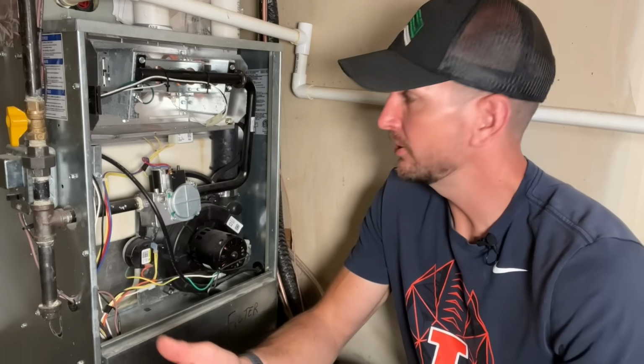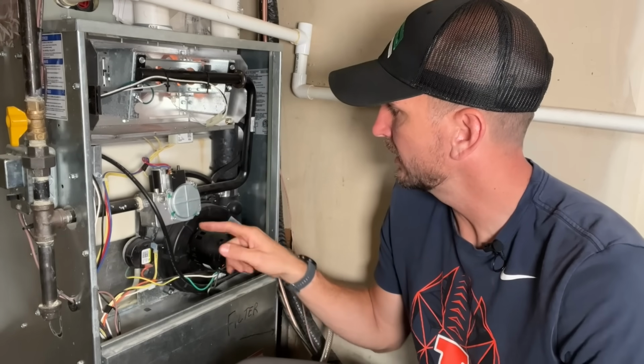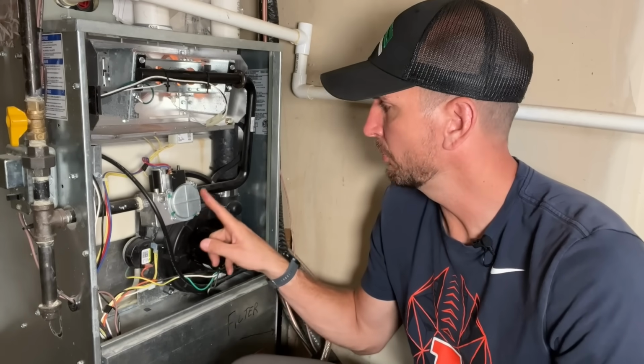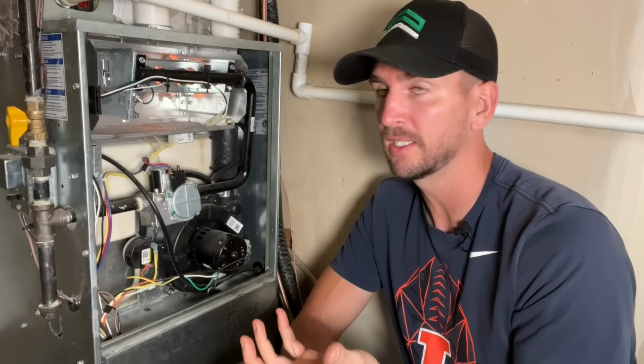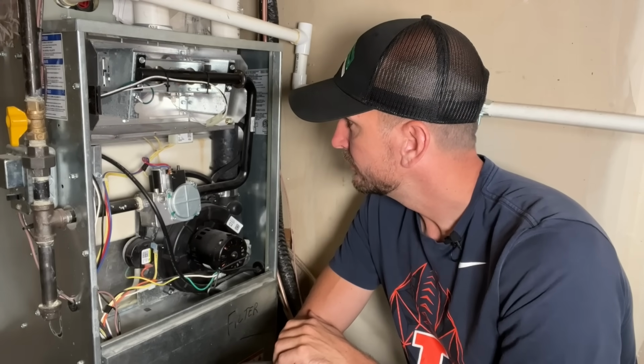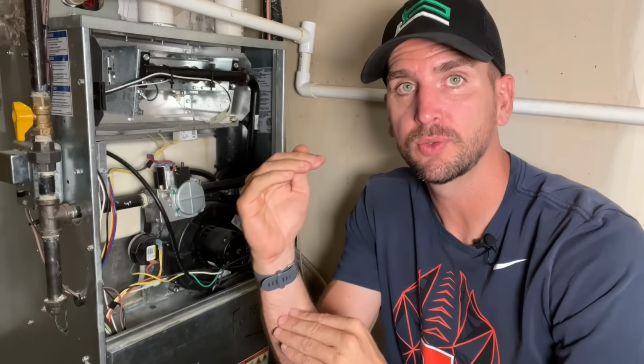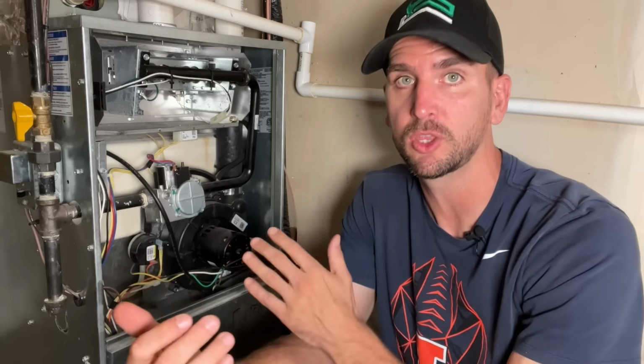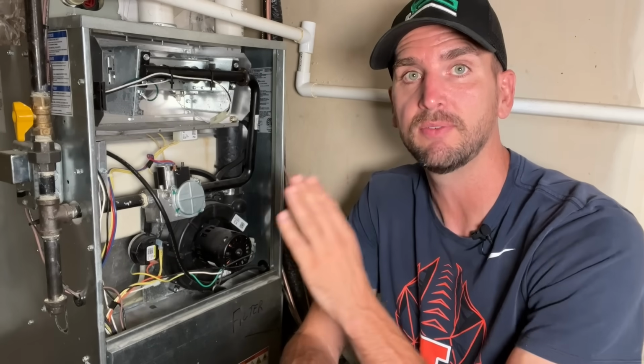and then test things out to see if that solved your problem. So just going through the standard steps again, we're on step 3 with that igniter, looking to go to step 4 with the gas valve turning on, and then the burner's actually lighting, and this time hopefully they stay lit for more than 2 or 3 seconds. So it looks like we're good and our problem is solved. Now, if you have rental properties where you're looking to avoid any long downtime on furnaces, or maybe just live in northern states, for the cost, it's probably not a bad idea just to have 1, 2, or even 3 of these flame detection sensors on hand so you can swap those out anytime you're having a failure mode like this.